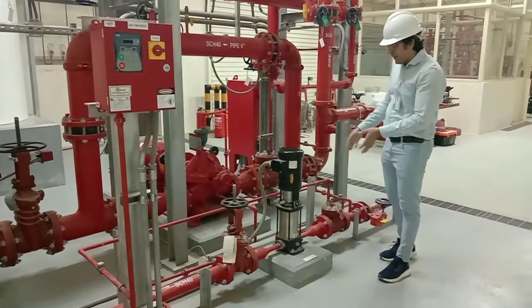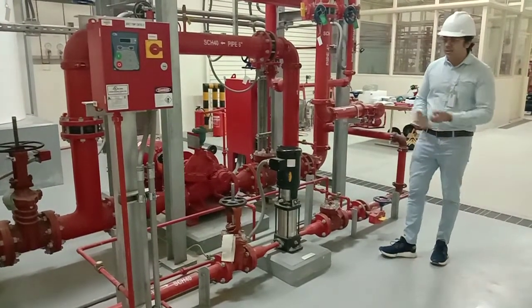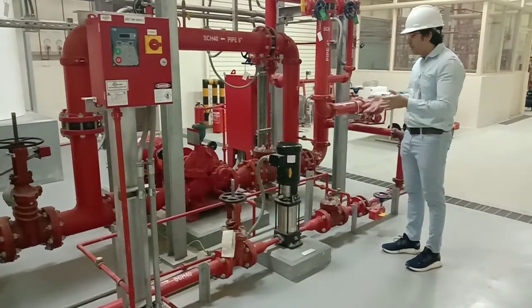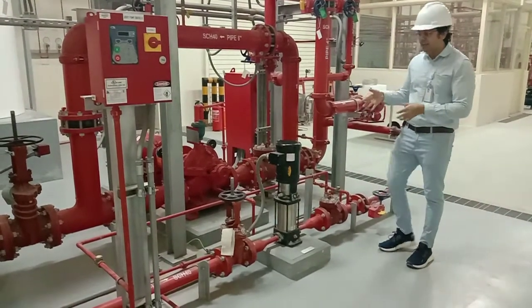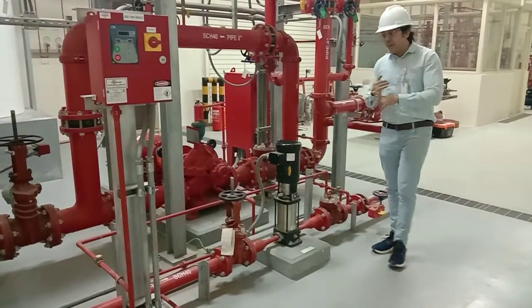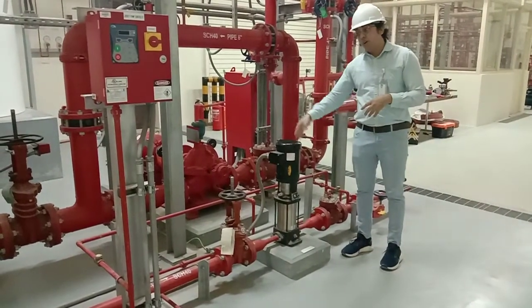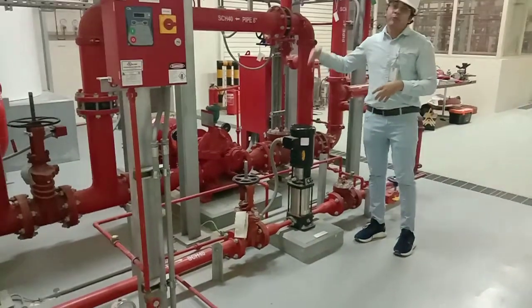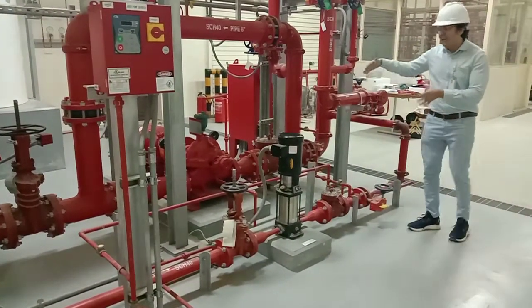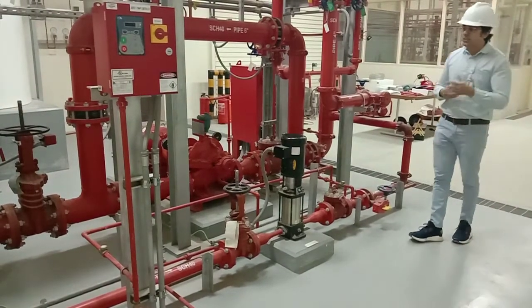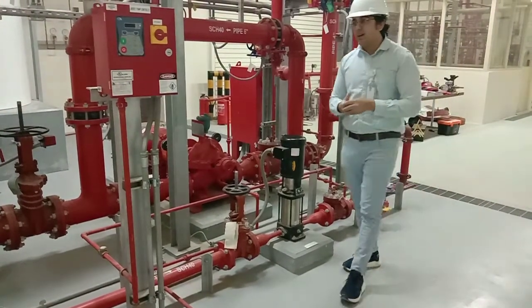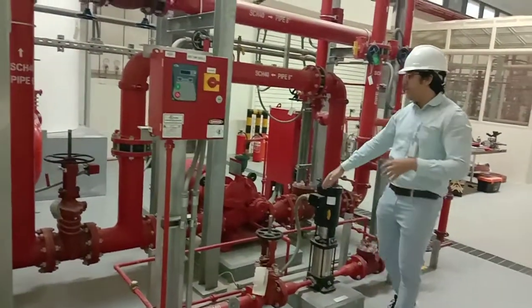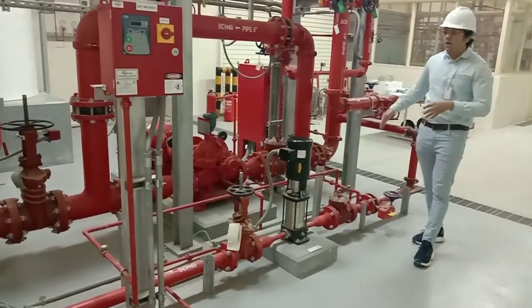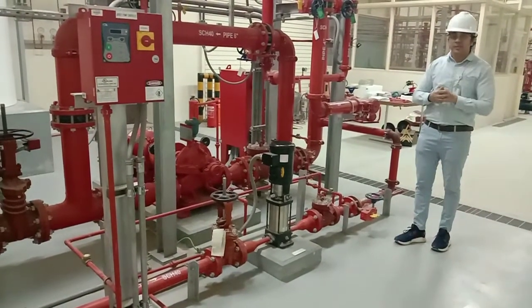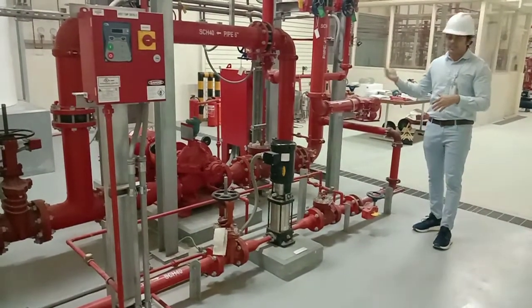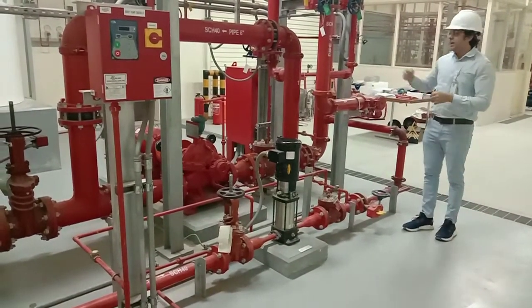Again, as I explained, it does not need to be listed, because the purpose of this pump is not to fight the fire, just to maintain the pressure. As per NFPA, we need a redundant pump. We have a jockey pump, we have electrical pumps, and we have a diesel pump, right? But we don't have a diesel pump at our facilities. I'm just explaining the sequence of operation. In case of a pressure drop, the jockey pump will start and maintain the pressure in the discharge piping, but it will only maintain a pressure difference of 10 psi. If the pressure changes by 15 psi, the main pump will start and supply water to the fire protection system.